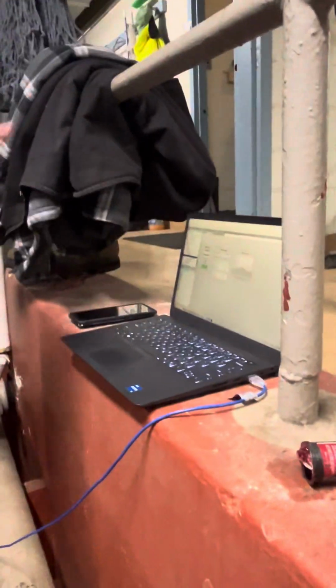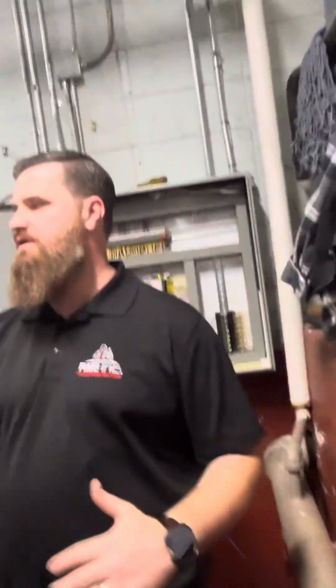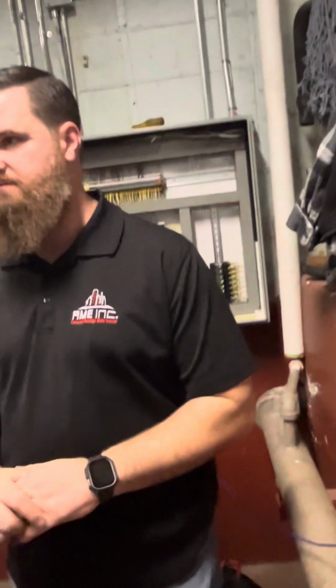Next thing we have is the vent fan control. As soon as this boiler system gets ready to fire a boiler, we have to turn these fans on. If this turns on, that fan automatically comes on, but it comes on after the fact, because we have no tie into this boiler. So if we're running one boiler, that's 25%, two boilers, 50%, 75%, 100% - that's 1, 2, 3, and 4. Does that make sense? So if you're running all 4 boilers, we run that at 100%.